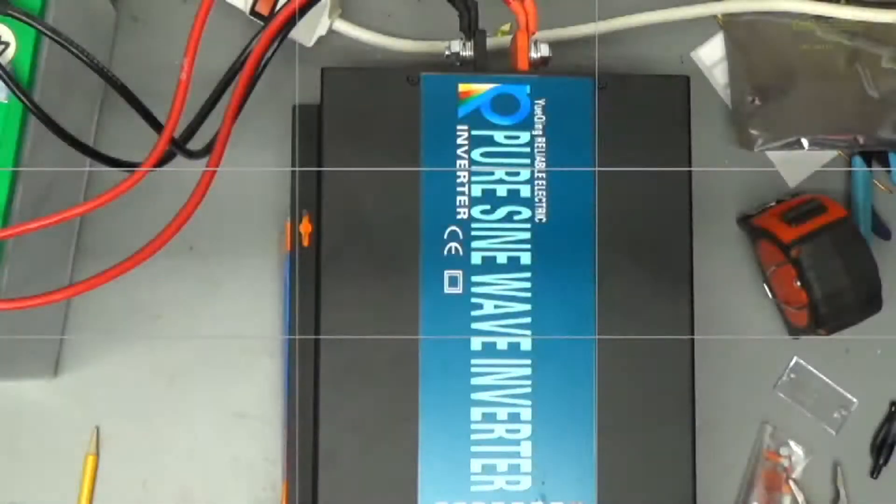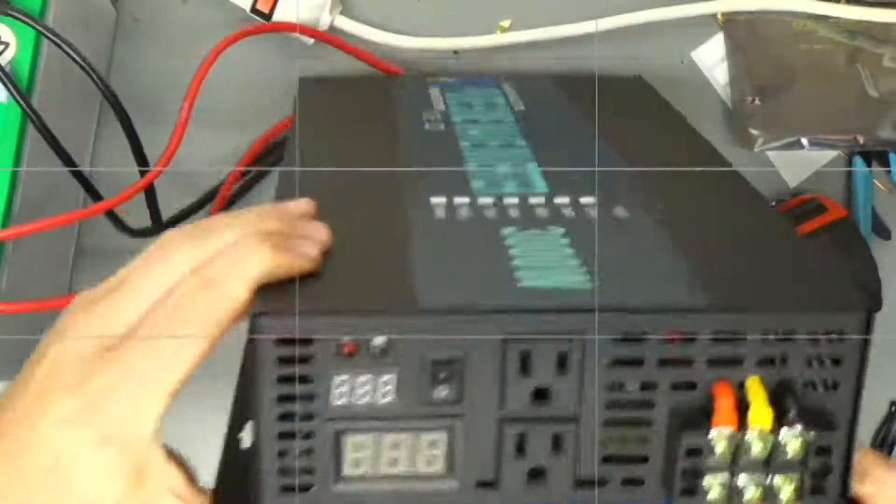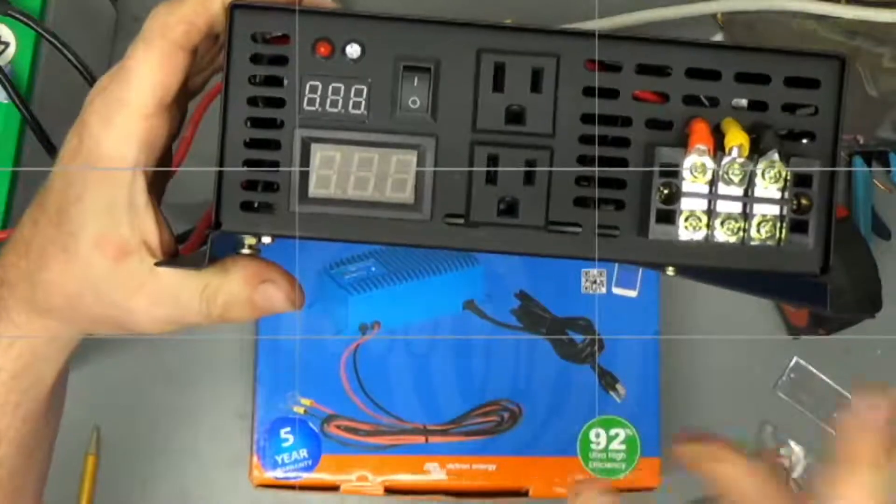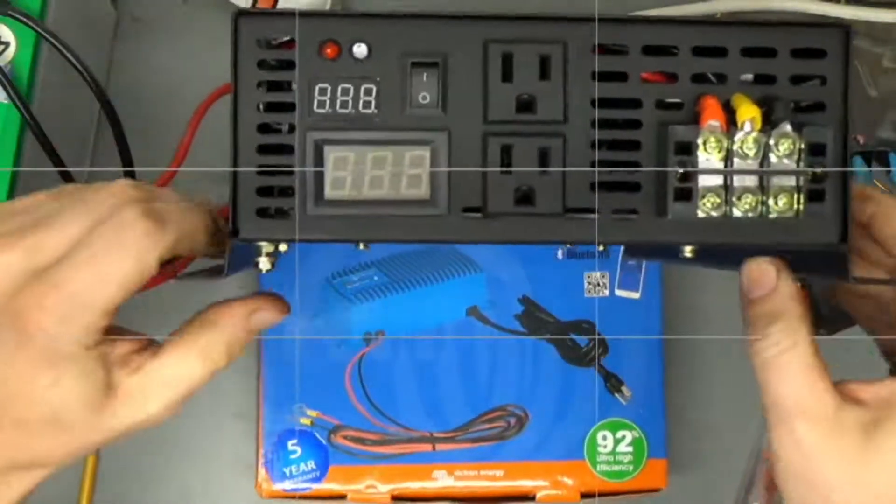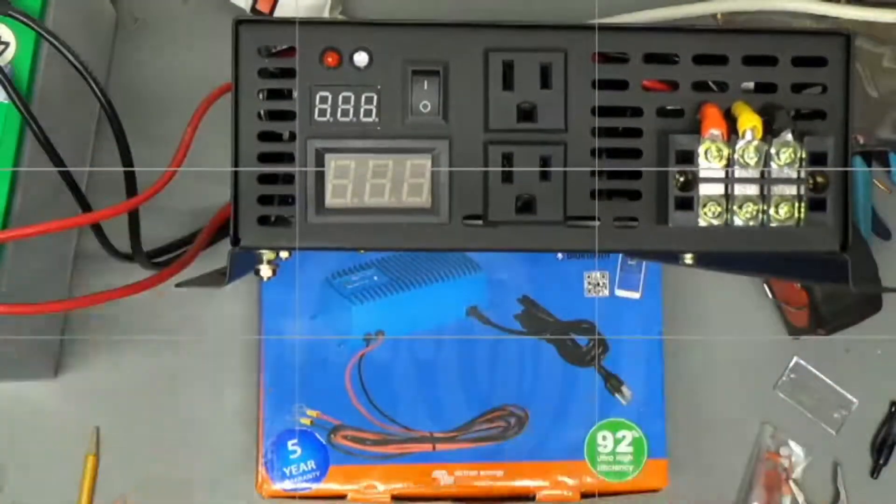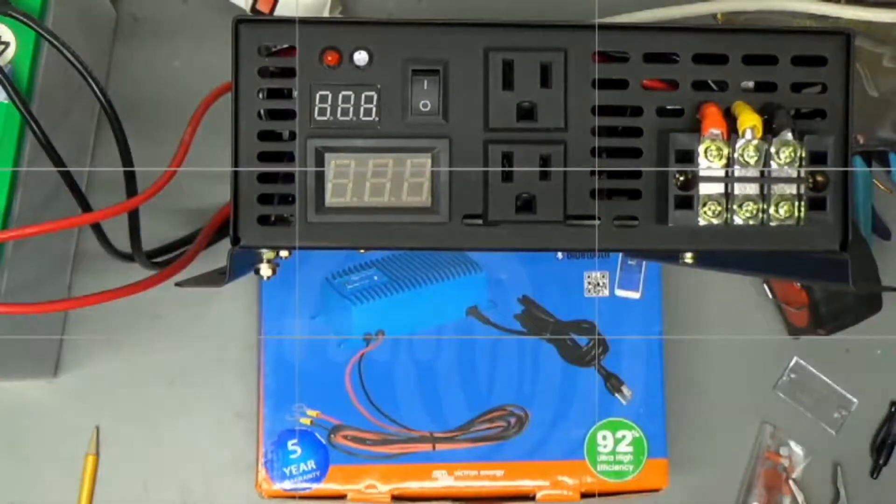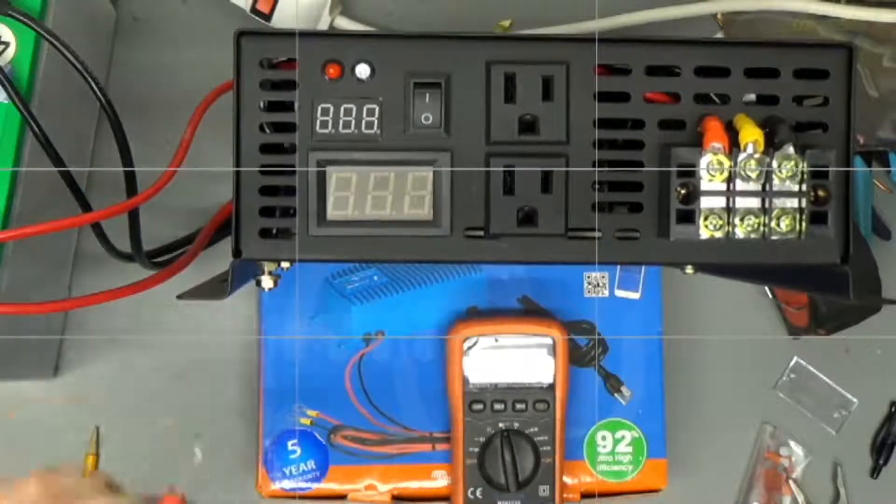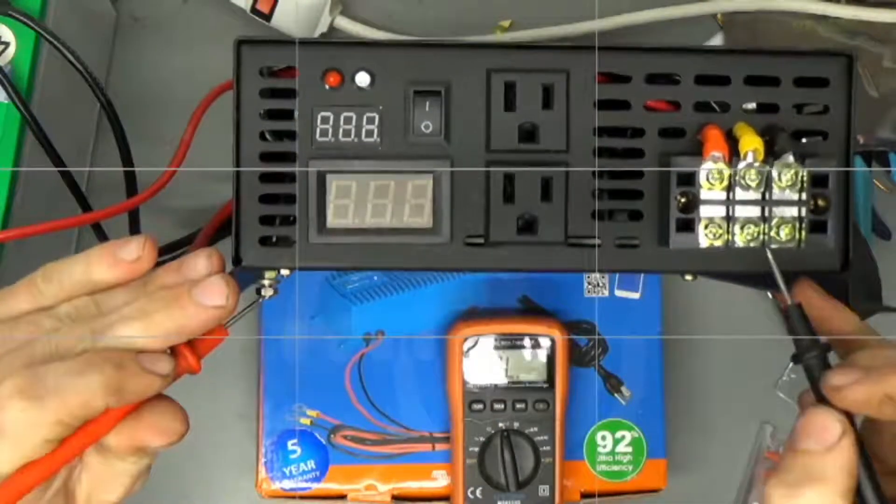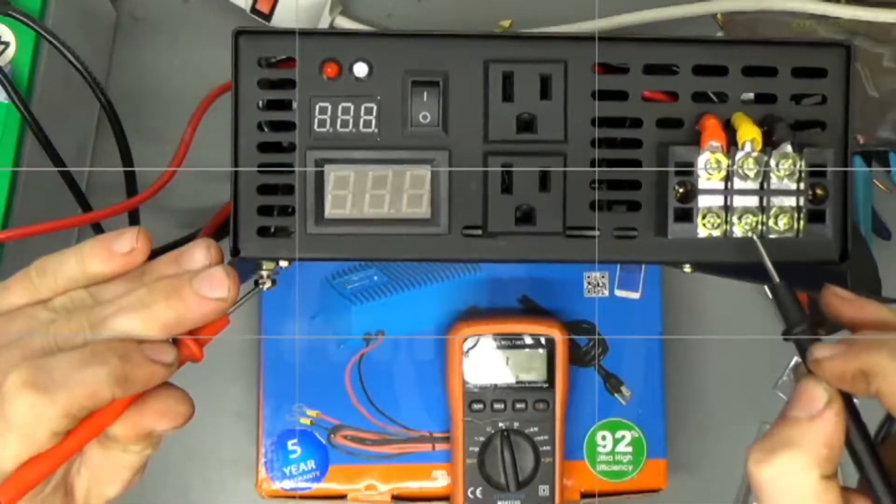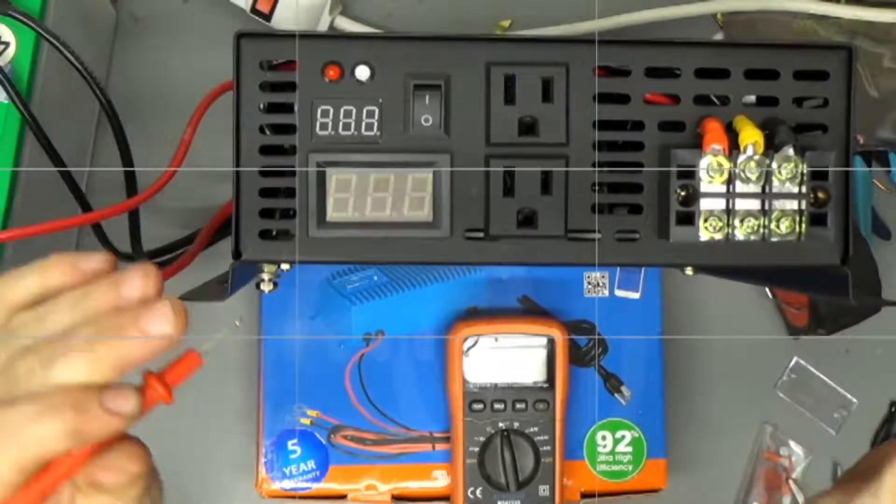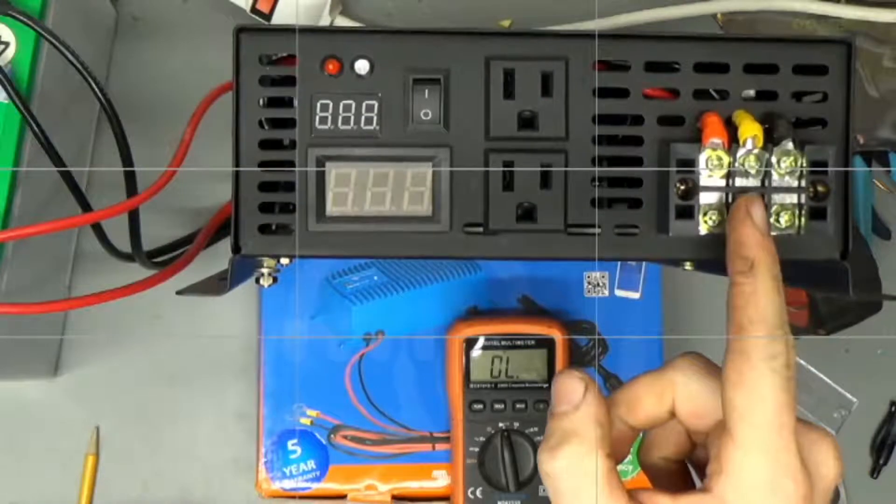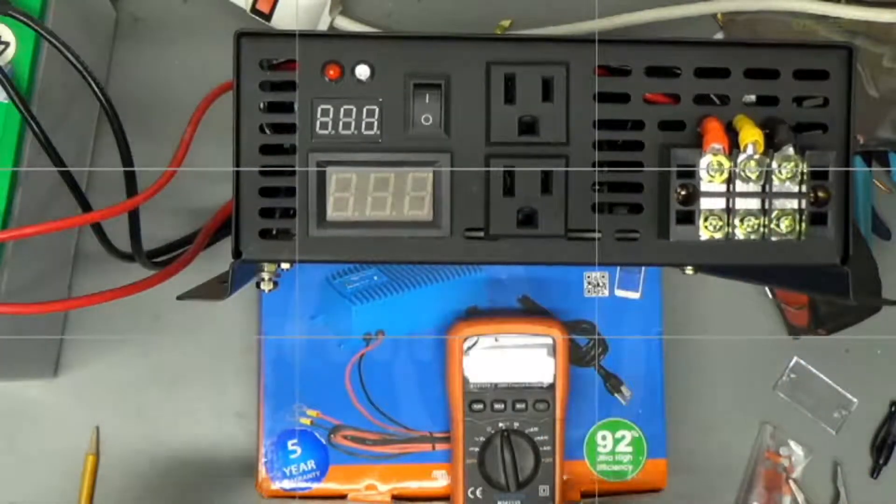And that generally works fine when you're just plugging shit into the receptacles because this is all isolated. Well, the case is grounded. The case is grounded to that so-called neutral. Let's check it and see. Yeah, okay, so the metal enclosure is attached to this so-called ground in the middle here.